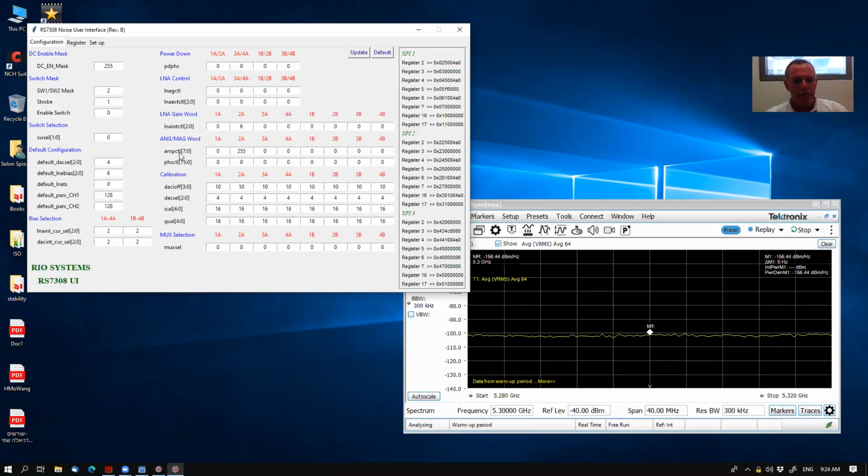So I have set the amplitude. Mostly for noise measurement, we will be setting the amplitude value. So we may disregard the other controls. Basically, the amplitude control sets the value of the amplitude of the output stage of the Core IC. And what is called LNA int control sets the value of the gain of the input stage of the Core IC. So these two settings vary the gain of the Core IC.